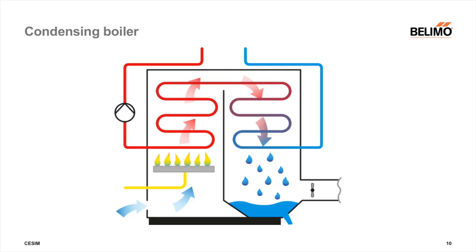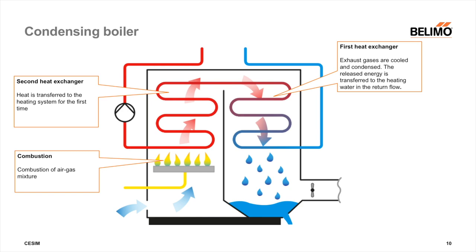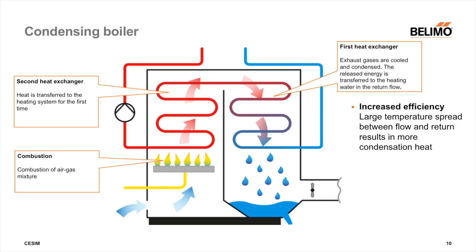A condensing boiler is a boiler for hot water heating systems which almost completely uses the energy content of the fuel used. In condensing boilers, the gas in the first heat exchanger is cooled as much as possible to extract the condensation heat of the water vapor contained in the gas. In the second heat exchanger, the water is reheated by combustion. The calorific value effect is achieved by low system temperatures, and due to the low return temperature, the gas is cooled and condensed.